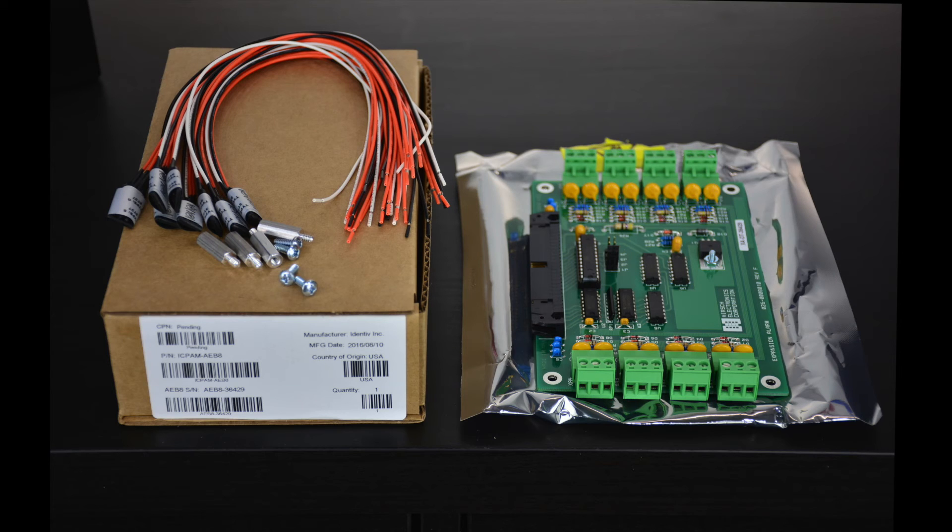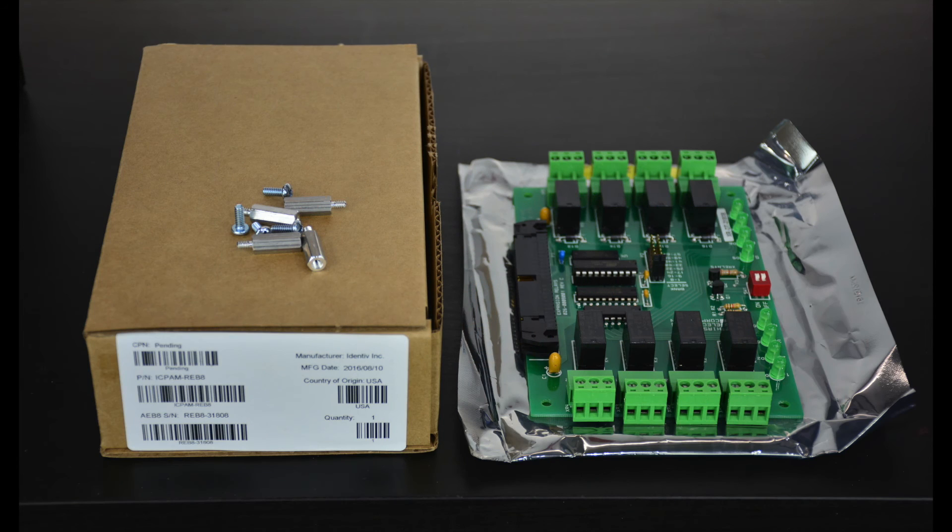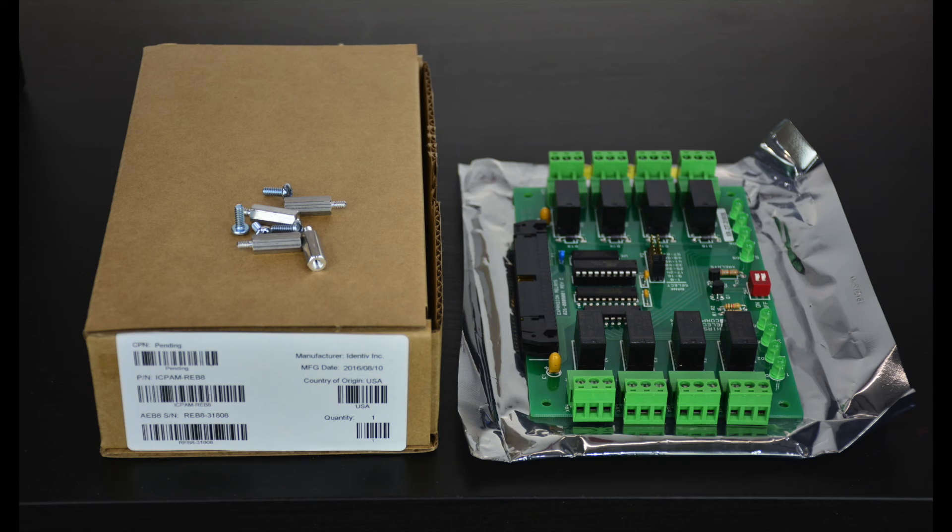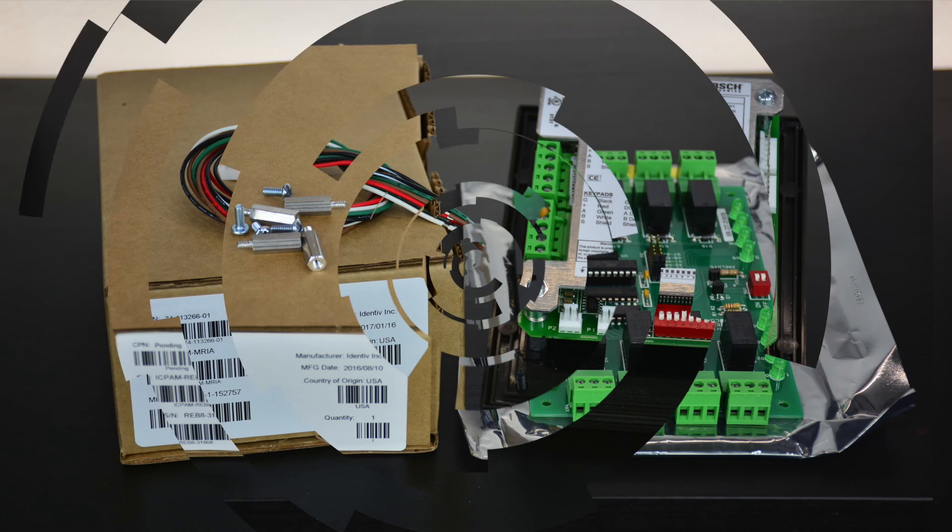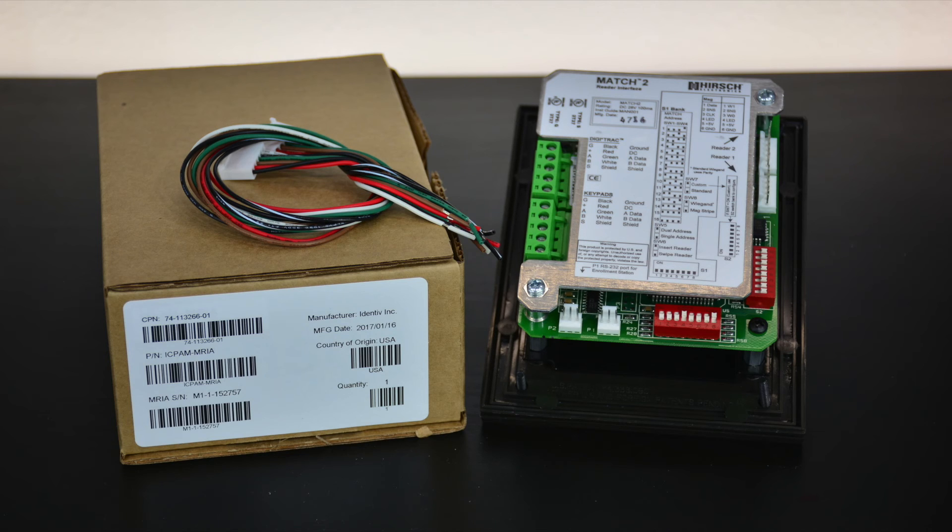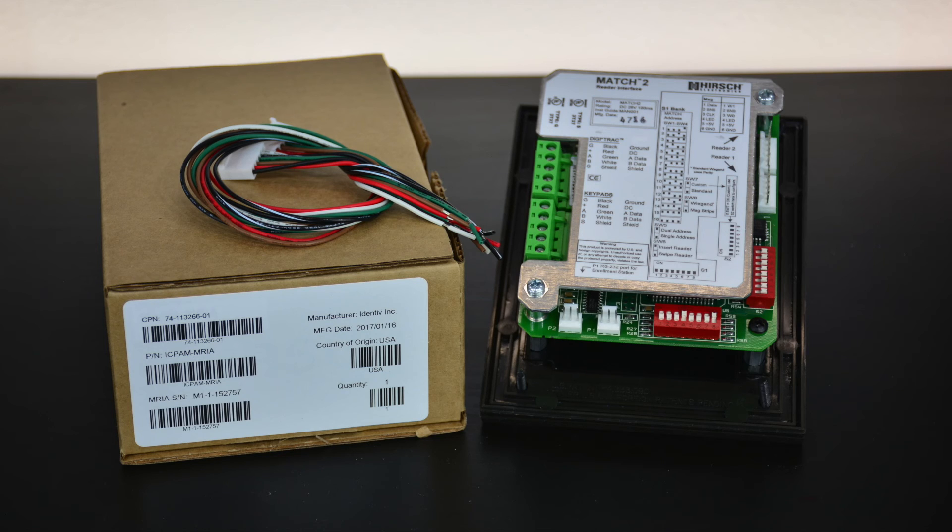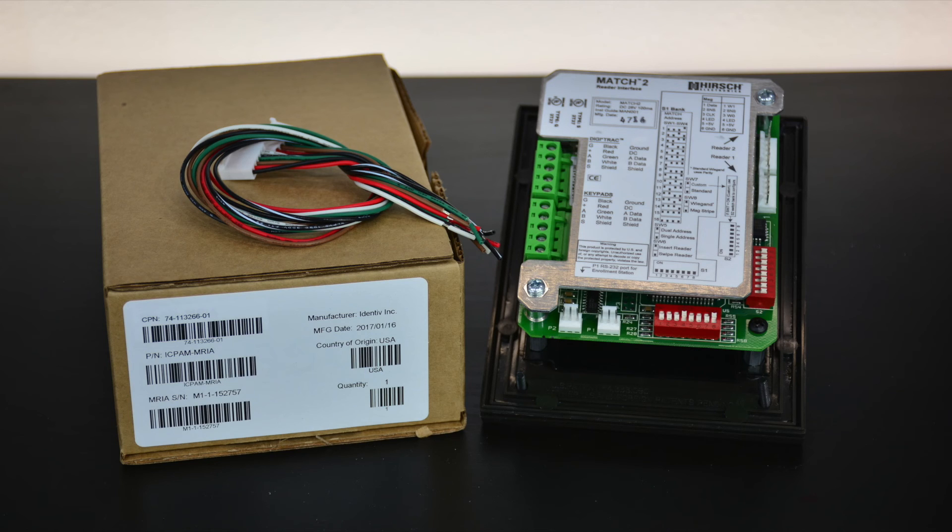The REB-8 is an eight-output expansion board. These can be used for general-purpose outputs. The MATCH2 reader interface board takes a match port from an MX or M series and provides two Wiegand ports for standard Wiegand readers. The MATCH2 board will be used with an MX when a door needs multiple readers for read-in, read-out, or if you have a reader that is farther than what standard Wiegand distance allows. The MATCH2 board would also be used with any of the M series controllers, such as the M64, to attach any Wiegand readers. The match port typically would run up to 1,500 feet or 500 meters.